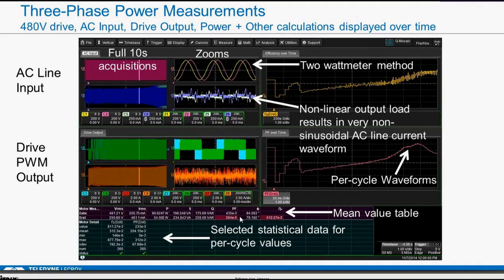And then power quantities are calculated. So you can see here the RMS voltage, 480 volts nominally for the three-phase system on the input, and about a fifth of an amp, or 200 milliamps, current, total three-phase. And then my drive output is a lot less. So this voltage on the output is only 250 volts, and it's drawing more current. These are my power quantities.